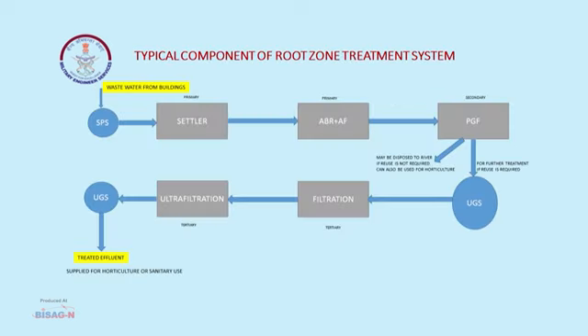This is the systematic diagram. You can see that wastewater comes from the building, goes to the SPS, then to the settler, ABR, anaerobic filters, PGF, then underground sumps, filtration, ultrafiltration, and finally to an underground sump from where it can be discharged for various purposes. We can directly discharge to rivers, or reuse for the flushing system, or reuse for horticulture purposes. All these components can be decided based on the reuse of the effluent.